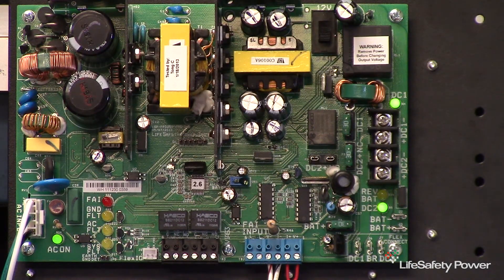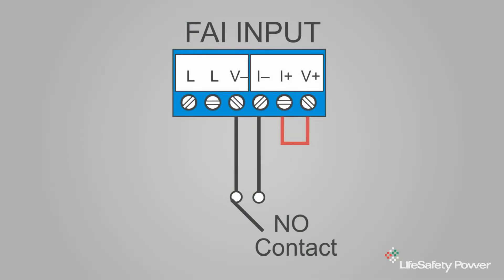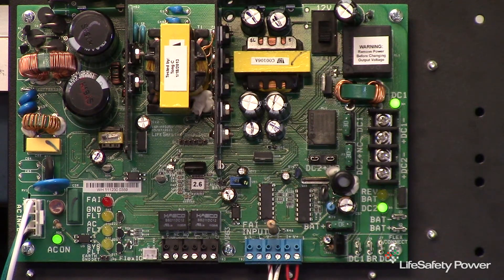For use with a normally open relay contact, place a small jumper on the blue FAI terminal strip between the I-plus and the V-plus terminals. With the board held so that the FAI terminal strip is on the lower edge of the board, these will be the two terminal positions located on the right side of the blue terminal strip. With a normally open relay contact and the FAI jumper in the normally closed position, the voltage at the DC2 output will be disabled when the relay closes. Note that the green LED is on initially and goes to off when the relay is activated, indicating that power has been removed from the DC2 output.